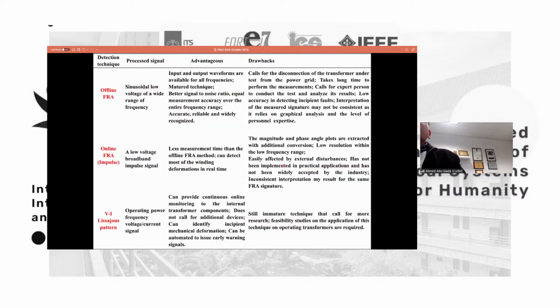I'll stop here with a simple takeaway from what I presented today. The current industry practice uses frequency response analysis, an offline technique that is accurate but has two problems: it requires taking the transformer out of service, and it's not very accurate for low fault levels. The second problem is that it depends on personal expertise, so different analysts may reach different conclusions for the same signature.